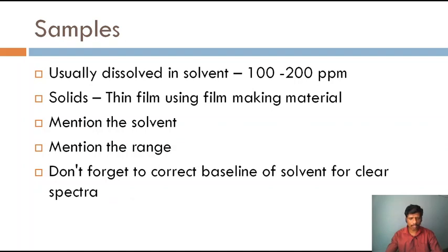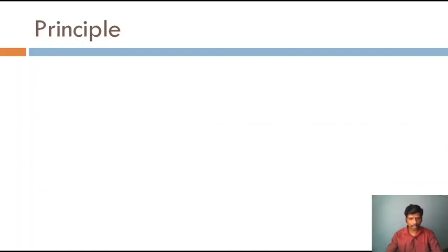In order to avoid noises in the spectra or unwanted peaks, you have to correct the baseline for the solvent. These are some tips for recording the samples. When you are recording the sample or you give it to an external source, these things you have to remember. These are the possibilities you have.